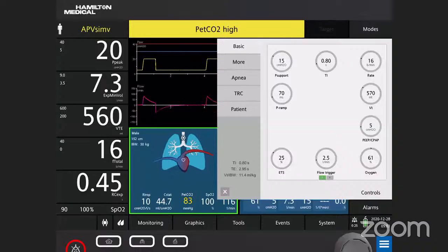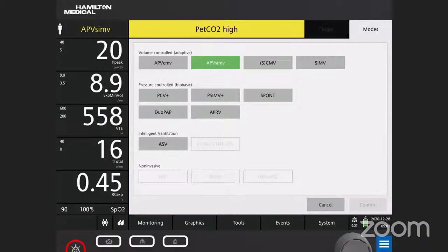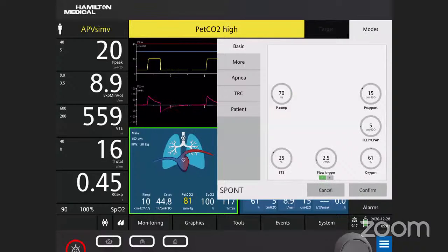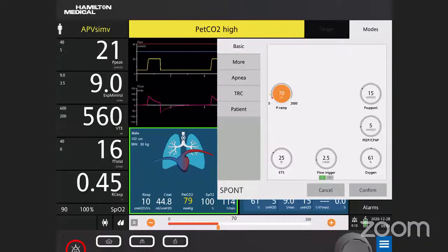So this has gone to this one. We will just go back. In a pressure support mode, you will be setting the pressure support level, the PEEP level, the oxygen, the flow trigger, and you will set the inspiratory rise time or the ramp time. We usually set around 200, that is, around 0.2 seconds. Okay.